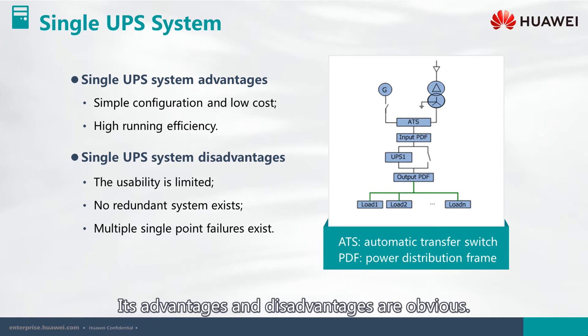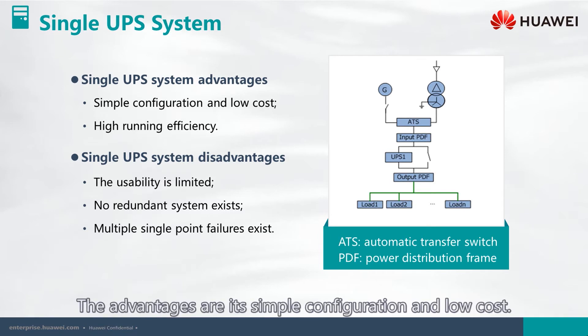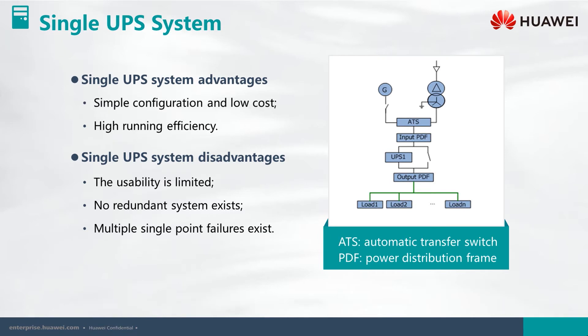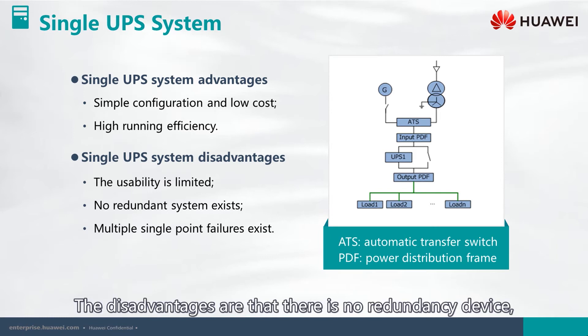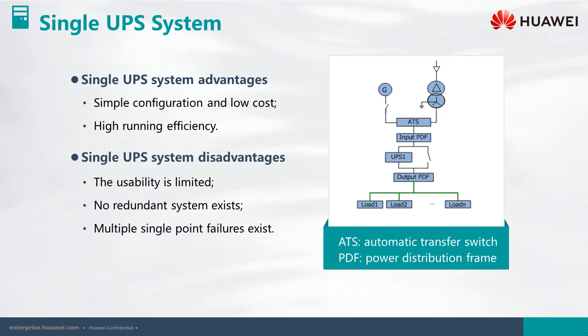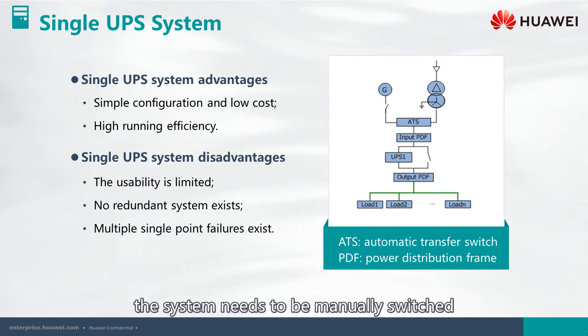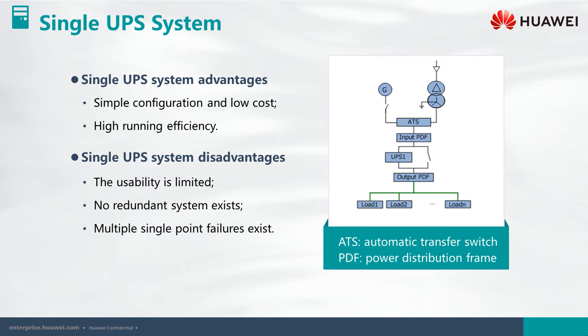Its advantages and disadvantages are obvious. The advantages are its simple configuration and low cost. The disadvantages are that there is no redundancy device, so when the UPS is faulty, the system needs to be manually switched to maintenance bypass mode, in which the loads are unprotected.